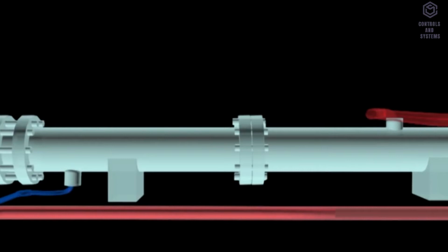After the heat is removed, the refrigerant as high pressure gas condenses into high pressure liquid and goes out from the condenser. The condenser most commonly used is the shell and tube type. Water flows through the tube, and the refrigerant liquid flows in the shell.